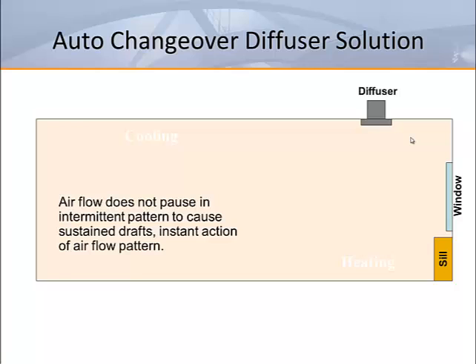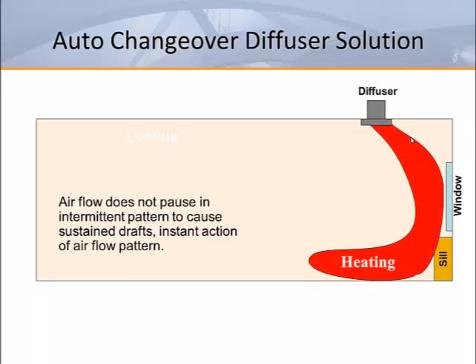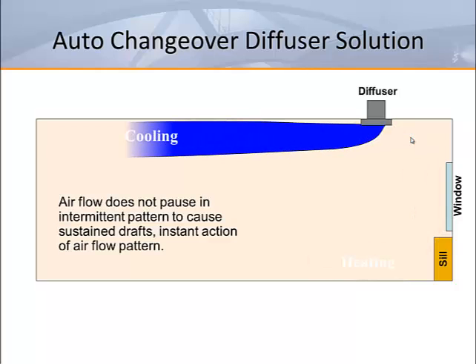While an auto changeover solution does not change the throw to 150 feet per minute or the 15-degree temperature requirement, the comfort in the occupied space during the heating can be improved with this option. All the warm air goes down the glass during the heating, or all the cool air goes across the ceiling during the cooling.